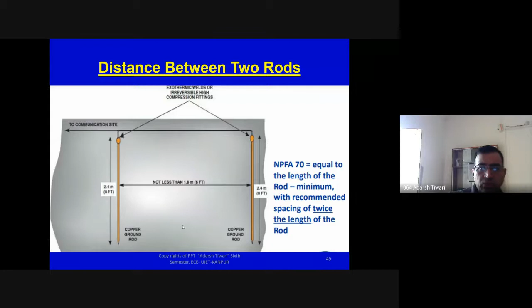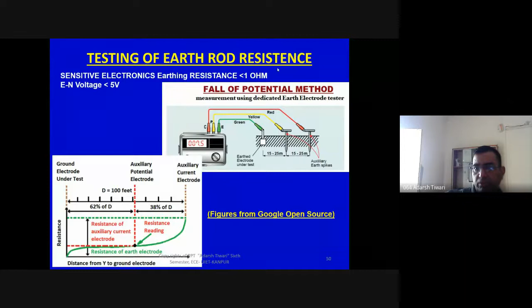Whenever the grounding is there, we have to test whether that grounding is good. Fall of potential is a very easy method, wherein this is the earth tester. These leads are there, and we can see directly on the meter what the resistance is. Normally for high-end electronics equipment, we would demand less than 1 ohm resistance of the earth pit.